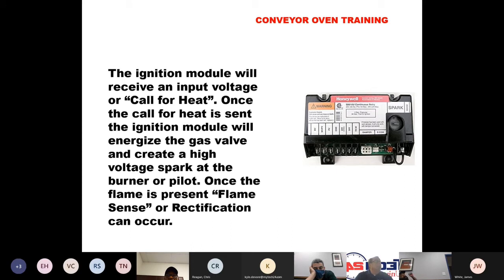So this ignition module is going to receive an input voltage or a call for heat. Once the call for heat is sent to the ignition module, it's going to energize a gas valve and create a high voltage spark at the burner or pilot. Once the flame is present, flame sense or rectification can occur. And at that point, the ignition module will send voltage to the main valve part of the gas valve to allow full flow of gas.